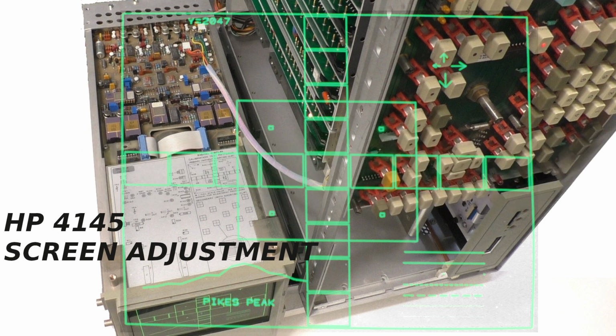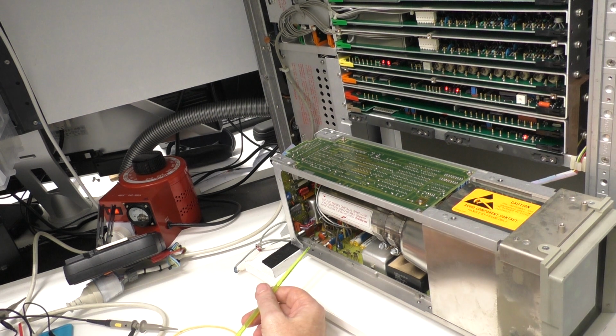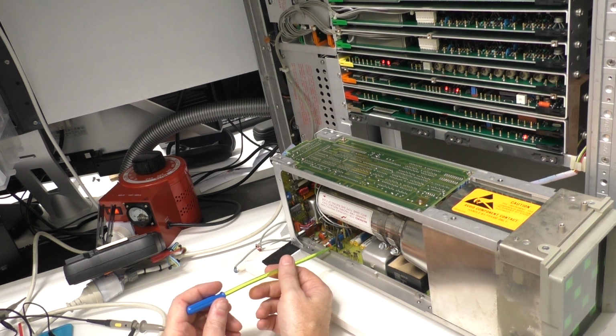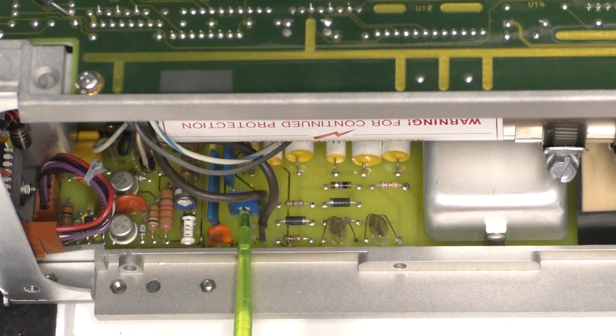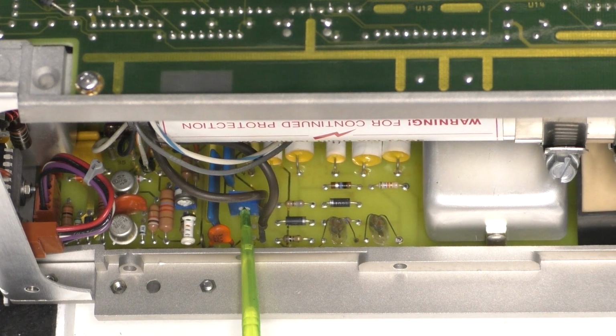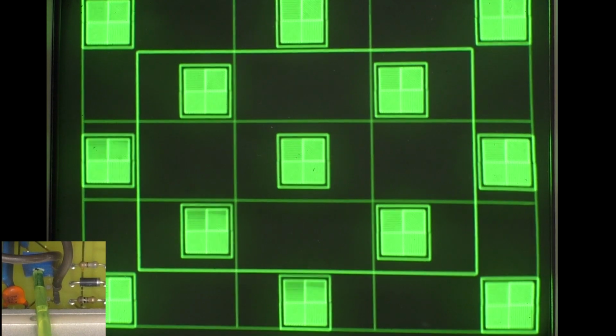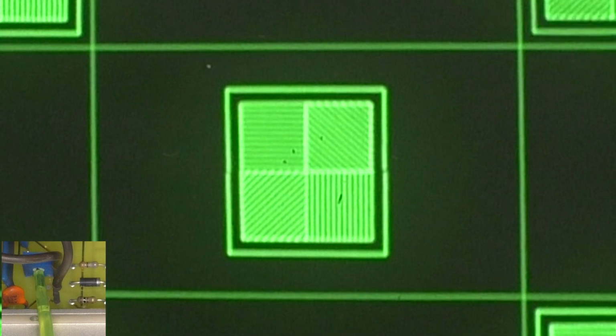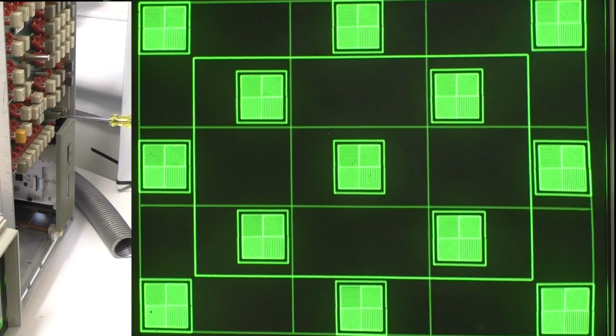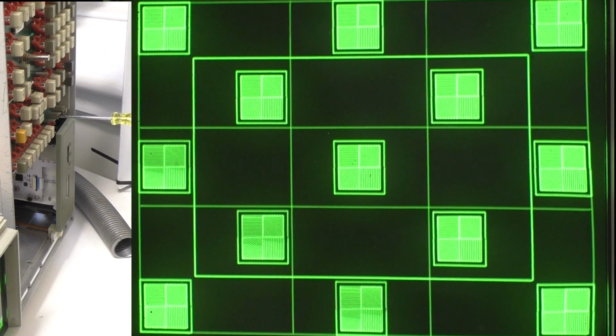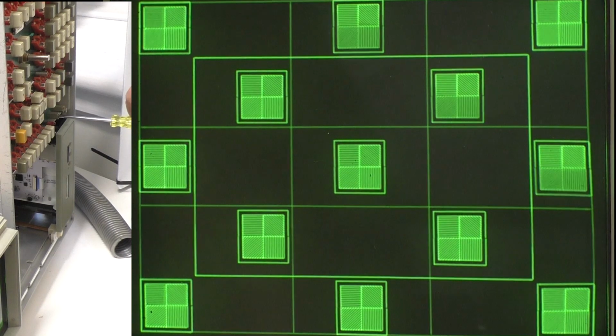For this test we will make an adjustment to the A4 high voltage board, put the display on its right side. Adjust the A4, R42 for optimum focus. You should be able to see the lines that make up the boxes of the test pattern. Adjust the intensity adjustment on the front of the unit. The focus of the pattern should remain the same throughout the full range of the intensity.